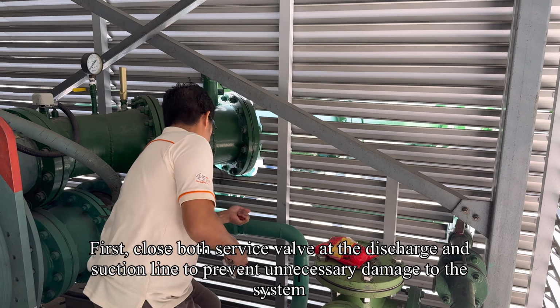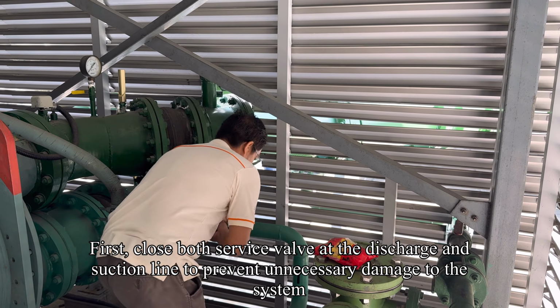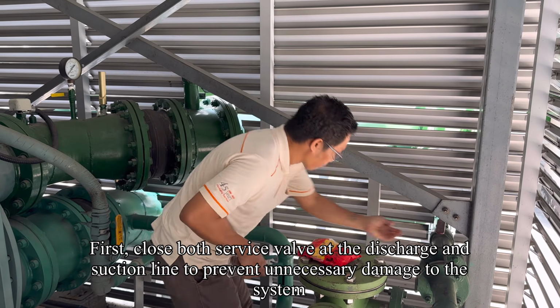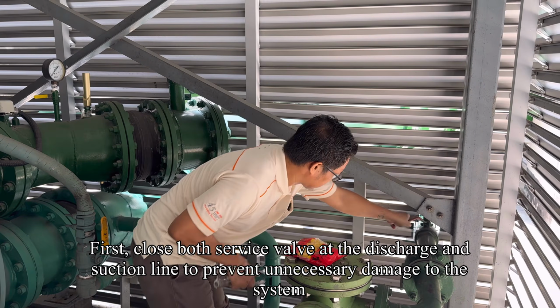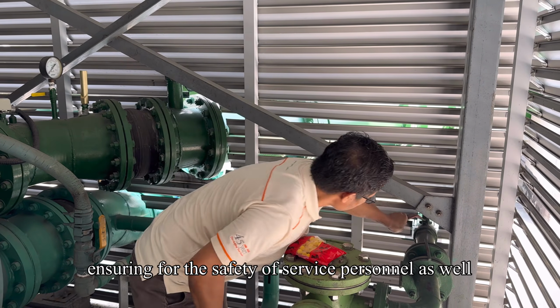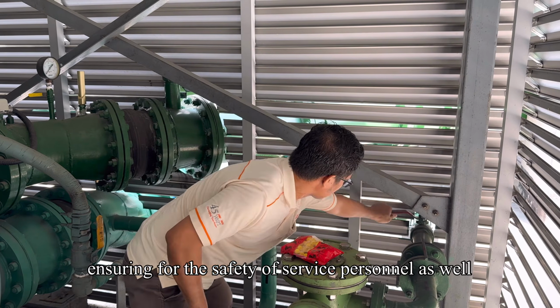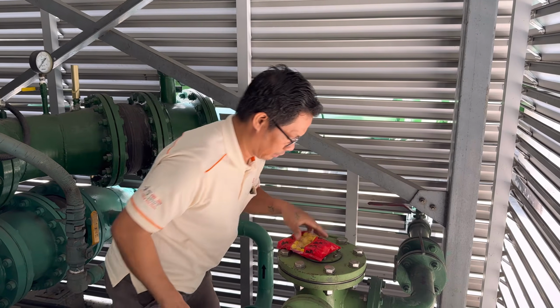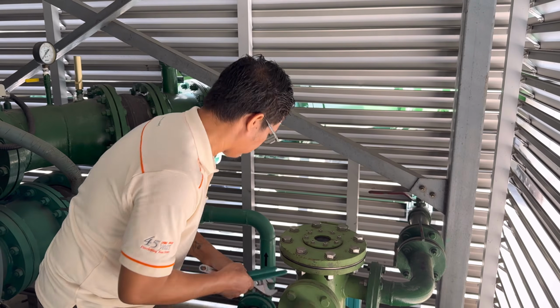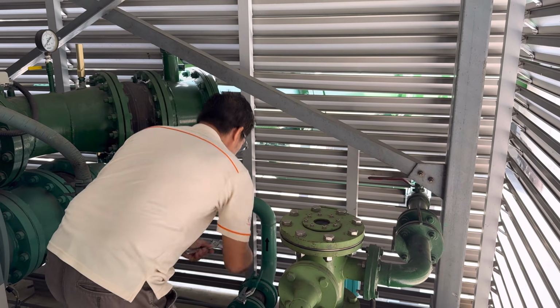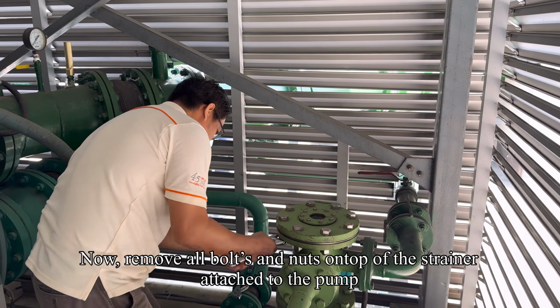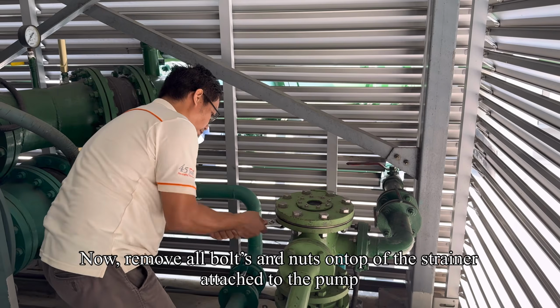First, close both service valves at the discharge and suction line to prevent unnecessary damage to the system, ensuring the safety of service personnel. Now, remove all bolts and nuts on top of the strainer attached to the pump.